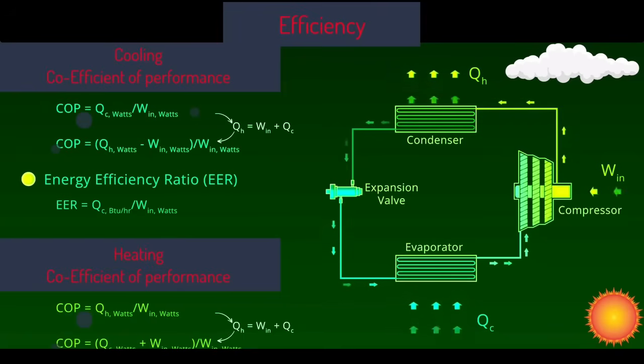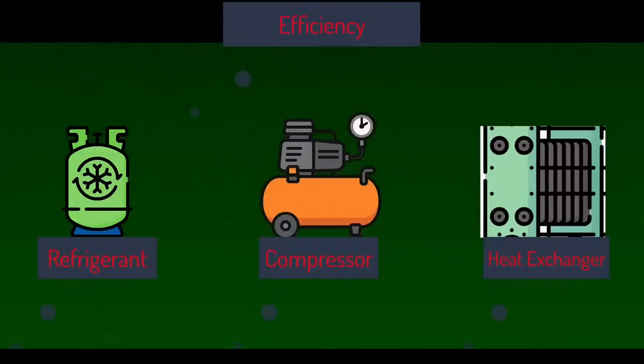EER uses imperial units while COP is dimensionless. A well-optimized system maximizes the heat absorption while minimizing the work input. In other words, a high COP or EER means a more efficient system. In practice, the choice of refrigerant, compressor type, and heat exchanger design all affect the system performance and environmental impacts.